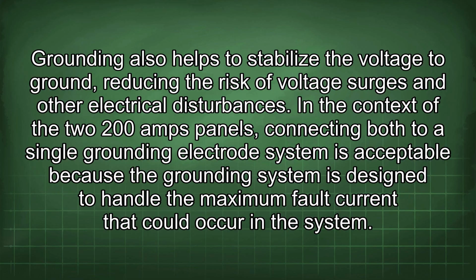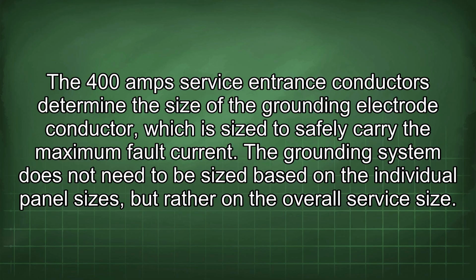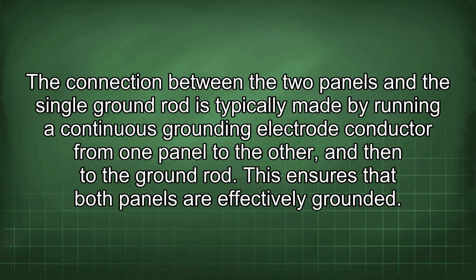In the context of the two 200 amp panels, connecting both to a single grounding electrode system is acceptable because the grounding system is designed to handle the maximum fault current that could occur in the system. The 400 amp service entrance conductors determine the size of the grounding electrode conductor, which is sized to safely carry the maximum fault current. The grounding system does not need to be sized based on the individual panel sizes, but rather on the overall service size. The connection between the two panels and the single ground rod is typically made by running a continuous grounding electrode conductor from one panel to the other, and then to the ground rod.